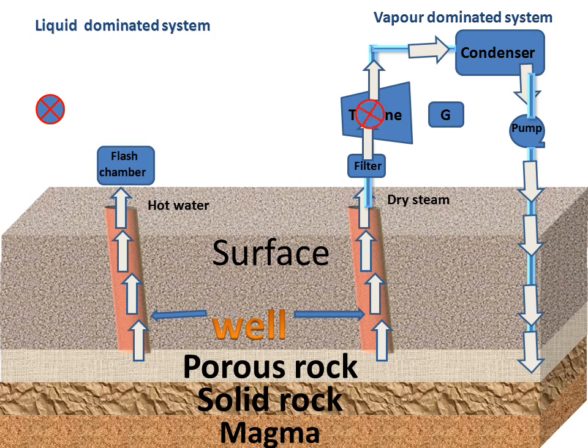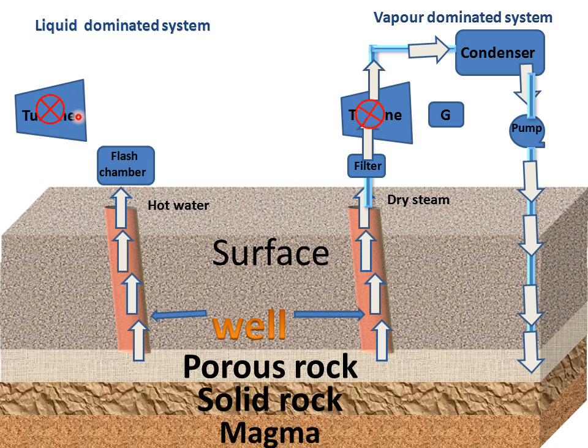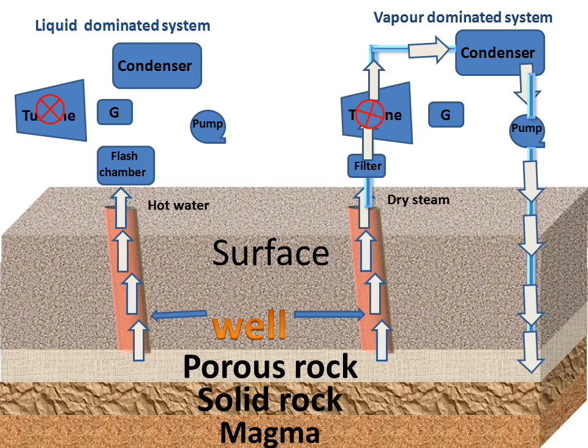In the liquid-dominated system, there will be a flash chamber for separating hot water and steam. Impurities in the mixture of water and steam are also separated in the flash chamber. Then we have a turbine for rotating, which is connected to the generator. After the steam leaves the turbine, it goes to the condenser for changing phase, and then we have a pump.